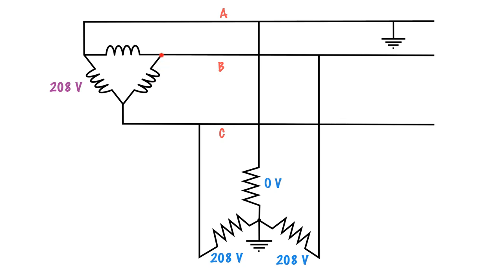A lot of times we see deltas now on transmission and not so much in distribution. So it makes it a little easier to chase down a ground fault when you can see a breaker trip, which would be in a Y configuration. But we still do have these delta systems out there, so you will see ground fault detection systems on these legs. And that's how we will determine which phase that we've got to go looking for. Suffice it to say that this transformer is not grounded, so that has a lot to do with it.